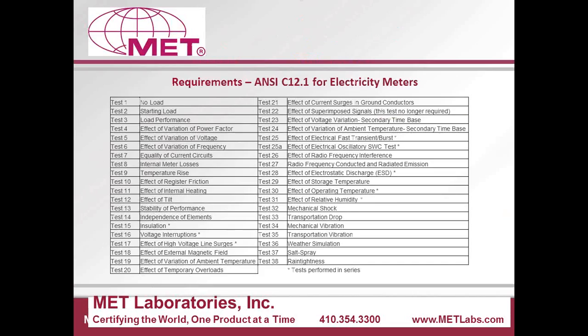So getting into the ANSI program, ANSI C12.1 and C12.20 have basically 38 tests listed in those standards, and you see that here in the table. Any given meter product would not necessarily be applicable for all of this testing. The important thing to note in this list of tests is there are a set of 8 series tests defined by the standard, and those are denoted by the asterisk there, if you can see that.